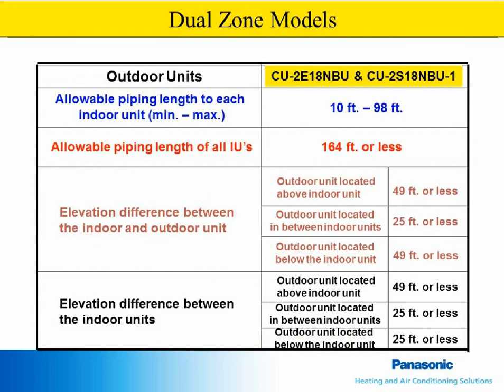There are several multi-zone models, and the dual zone is shown in this example. It has the same limitations as a single zone, but with a few additional variables to consider. There's a maximum distance from the outdoor to one indoor, and in this case, 98 feet. If you add up the length of pipe from the outdoor unit to all indoor units, there is a maximum total, and in this example, it's 164 feet.